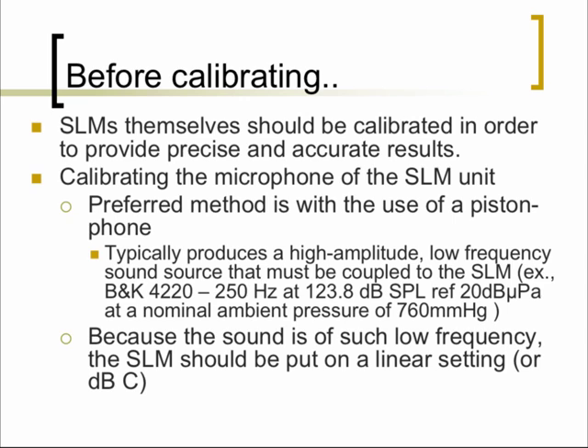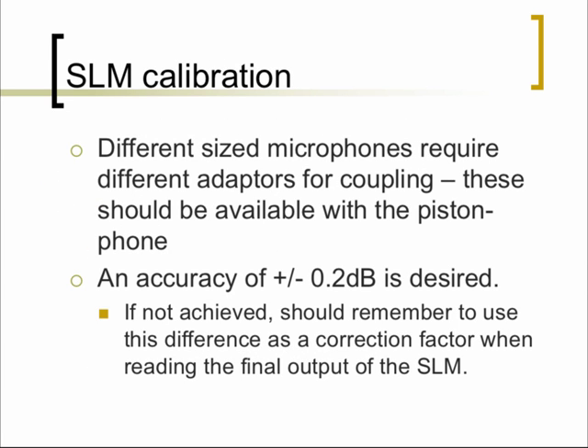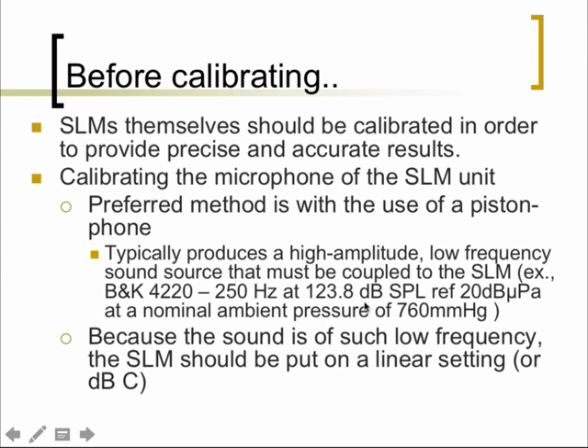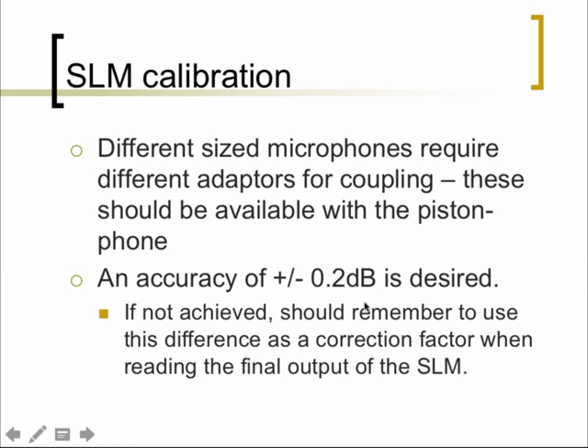If that piston phone is connected to the sound level meter and engaged, the output of the sound level meter should read exactly 123.8 dB SPL. If it reads anything different, one would have to use a correction factor. Different sized microphones require different adapters for coupling. What is permitted is a plus or minus 0.2 dB tolerance. If the reading is outside that range, a correction factor must be applied for the final output when doing audiometric calibration.